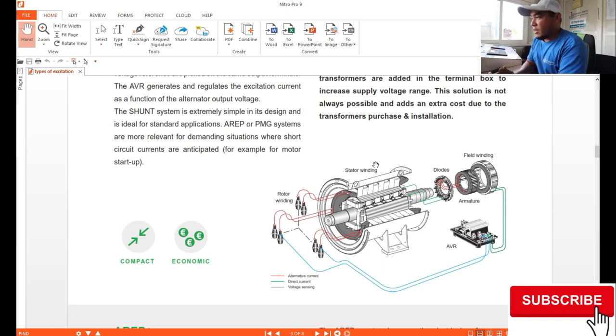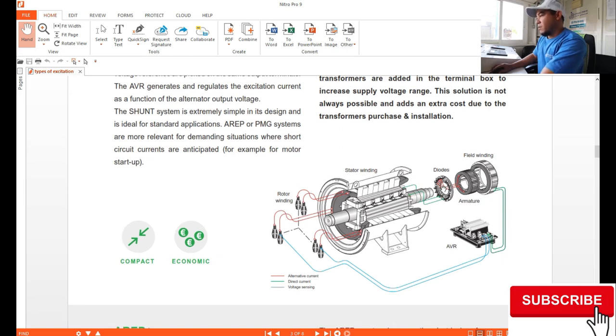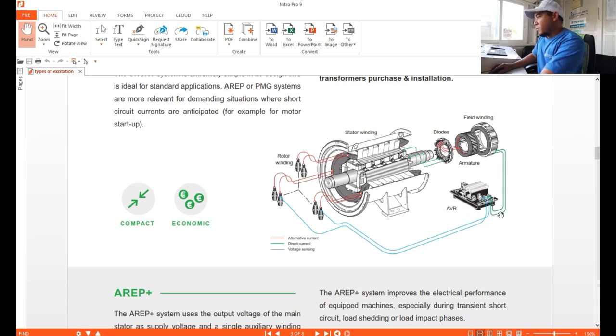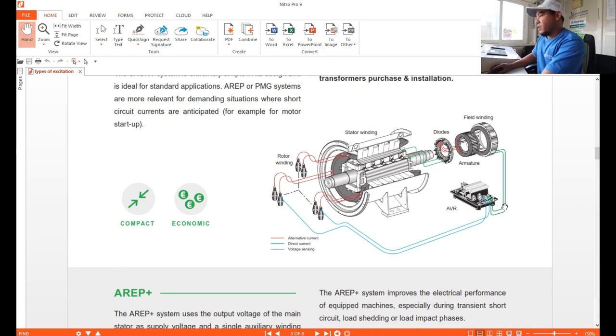The shunt AVR is fully controlled by the AVR itself — it generates and regulates the excitation current as a function of the alternator output. The connections are very simple and easy to identify because we have only four wire connections: F1 and F2 connected to the exciter field, while the sensing is connected to the sensing terminals. That's it — just the sensing and exciter field connections.